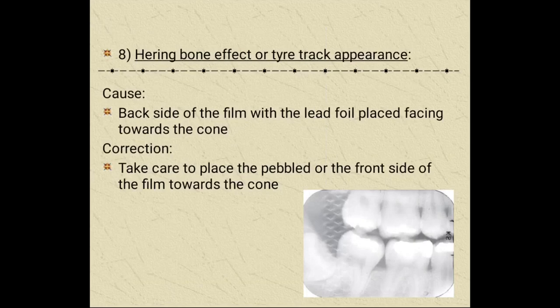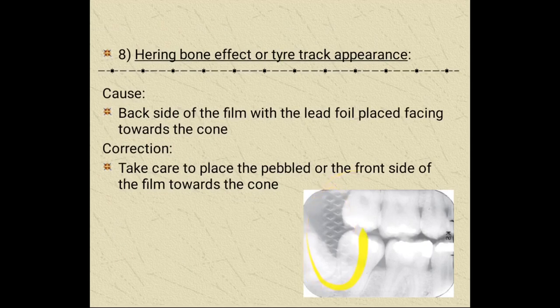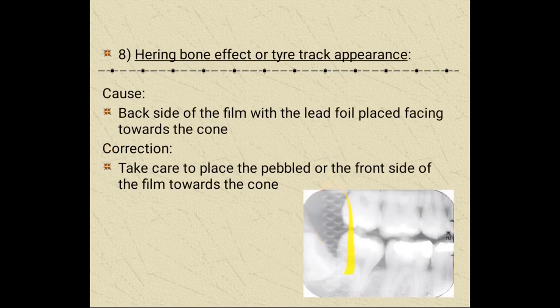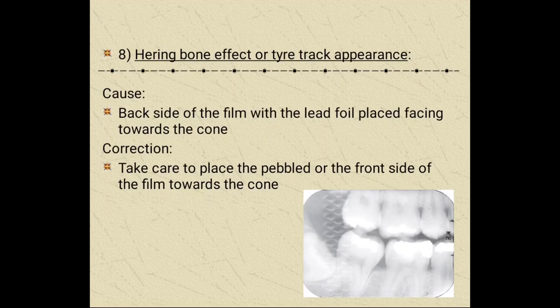A very important finding is the herringbone effect or tire track appearance. It is due to the backside of the film — with the lead foil — being placed facing towards the cone. It should be vice versa. We should take care to place the pebbled or front side of the film towards the cone. When the opposite side is placed towards the x-ray beam, the tire track or herringbone effect will appear. This herringbone effect is very important to know.